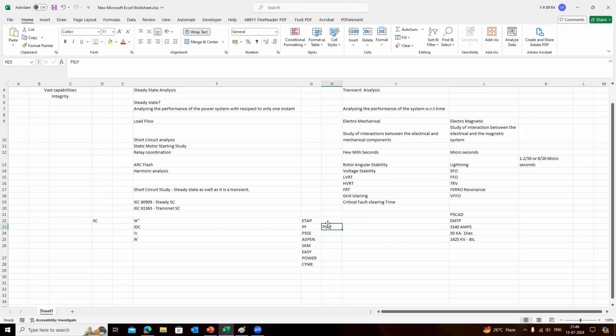These softwares can be used to perform almost all studies, except PSS/E. With PSS/E we can only perform load flow, short circuit, and stability studies, but not motor starting. It will also not be able to perform relay coordination, arc flash, and harmonic analysis, because PSS/E is basically meant for utility applications, limited to load flow, short circuit, stability, and RMS.